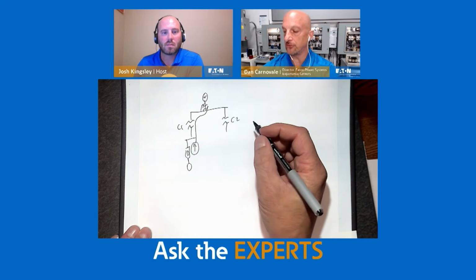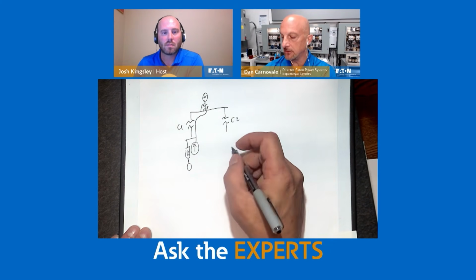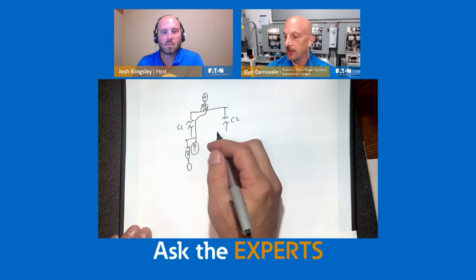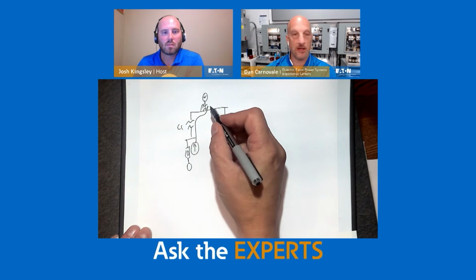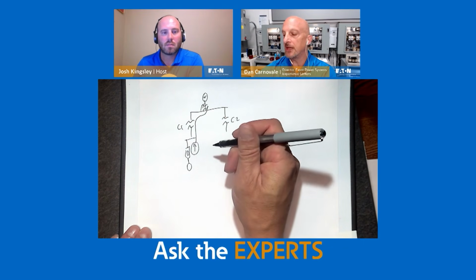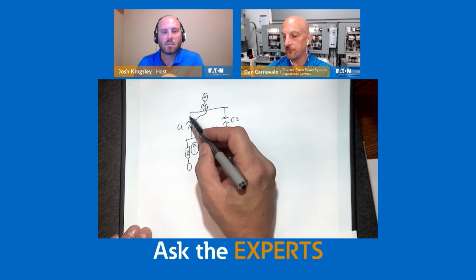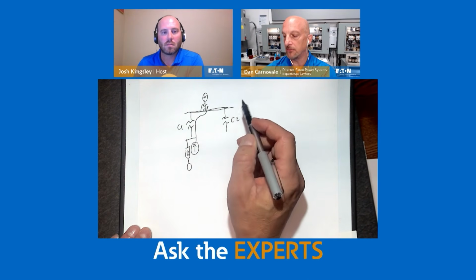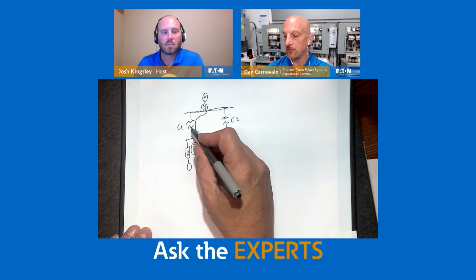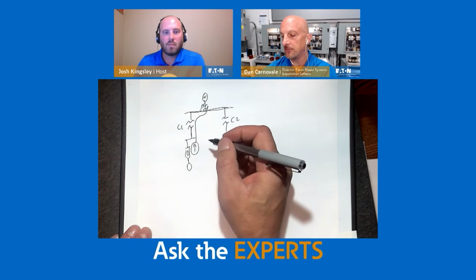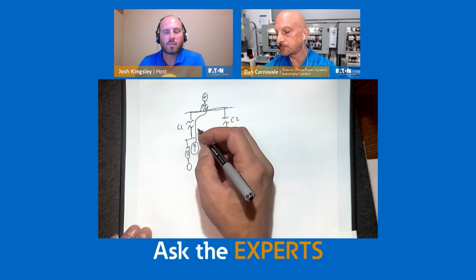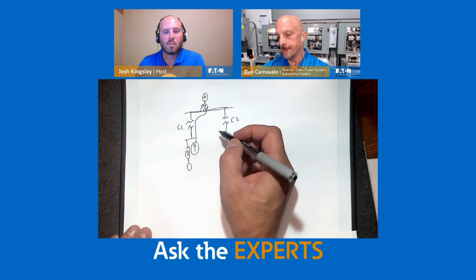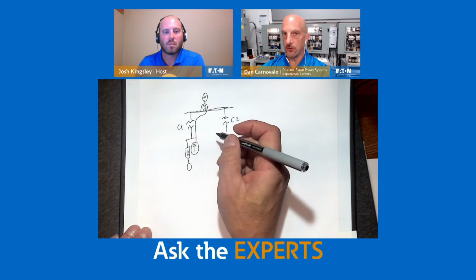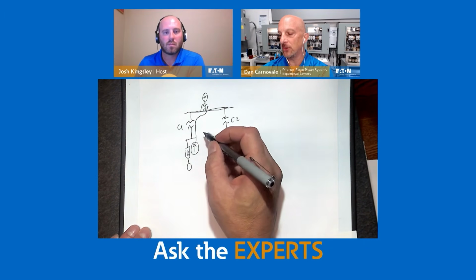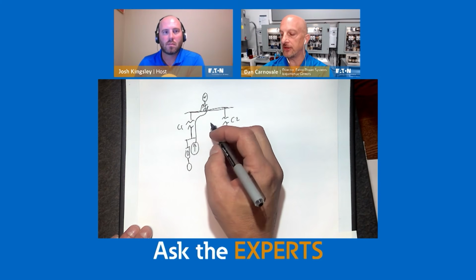So there are tables in the IEEE 519 standard that basically define the current distortion that you're allowed to push up through your system and the voltage distortion that you're allowed to create at the common point, at the point of common coupling. So sometimes it's on the primary of the transformer, sometimes it's on the secondary, depends. But when you think about it, it's all related more to voltage than current. And people say, well, why would you say that? And it really becomes this.